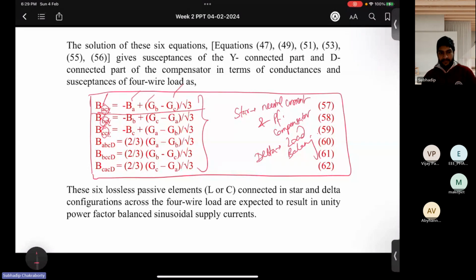So from them, if someone gives you the kind of loads that are connected and says I want these features, that is neutral current, load balancing and power factor compensation, then give me the compensator values. Then you need to determine the star and delta sets. If they ask for star only, give the star values, and if delta, give only the delta. So remember, all these values will be different because they depend on the type of load. However much load you put in one phase, the value of the compensator for that phase will be different. So these are dependent on the loads. Please remember, all the values may be different for the three different sets.